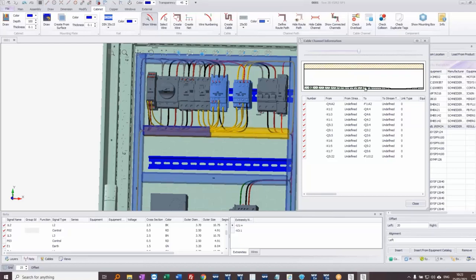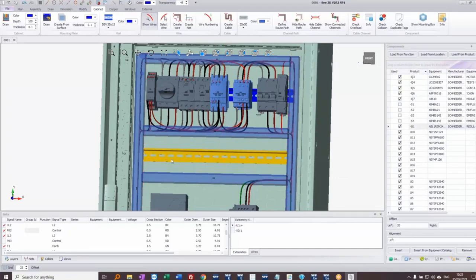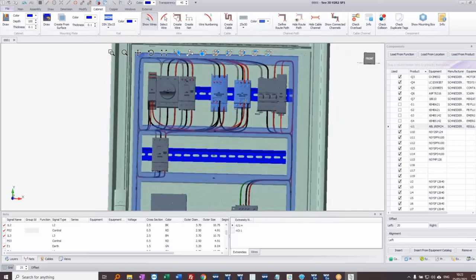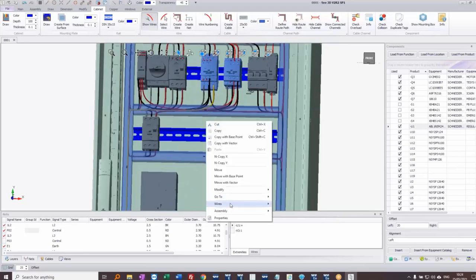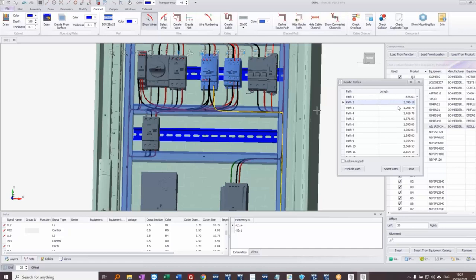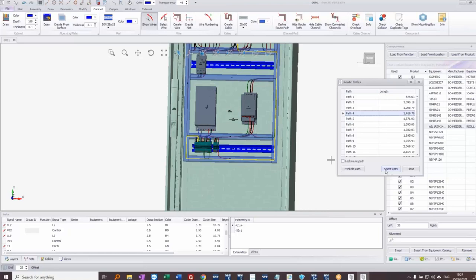If a wireway is overpacked, it will show up here and you can do an overall check for overloads. You also get a detailed view of which wires go via each wireway. If I move a component — double-clicking and dropping it lower — the wires automatically reroute, potentially reducing congestion in a particular wireway. I can also select an individual wire, right-click, and choose a different routing path, seeing the length difference for each alternative. I can select a path and lock it so auto-routing preserves it.